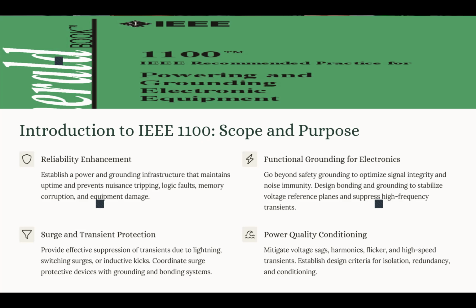Now, the key objective of IEEE 1100 is to keep sensitive electronic systems running continuously without any unexpected shutdowns, data loss, or malfunctioning. How we do that is by designing the power distribution and grounding system so we avoid unintentional or unexpected tripping or breaks. We design the system to prevent logic faults, for example in microprocessors, to minimize memory corruption in digital systems, and to protect the equipment from physical damage because of power disturbances like surges or harmonics.